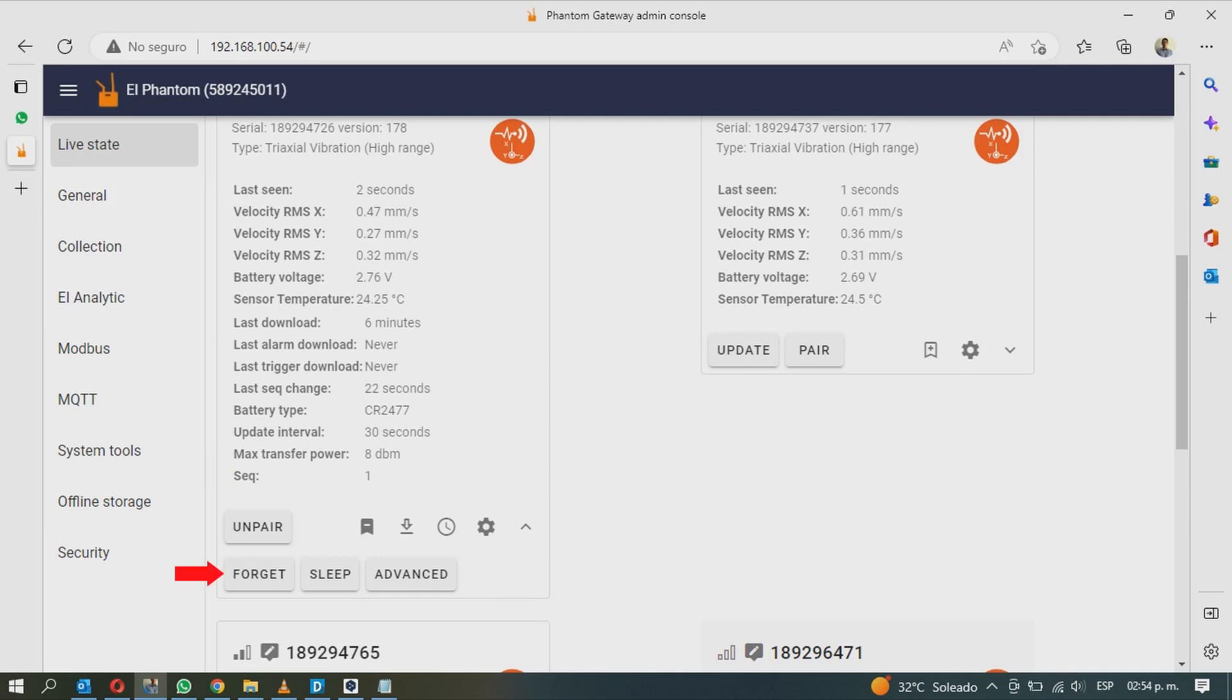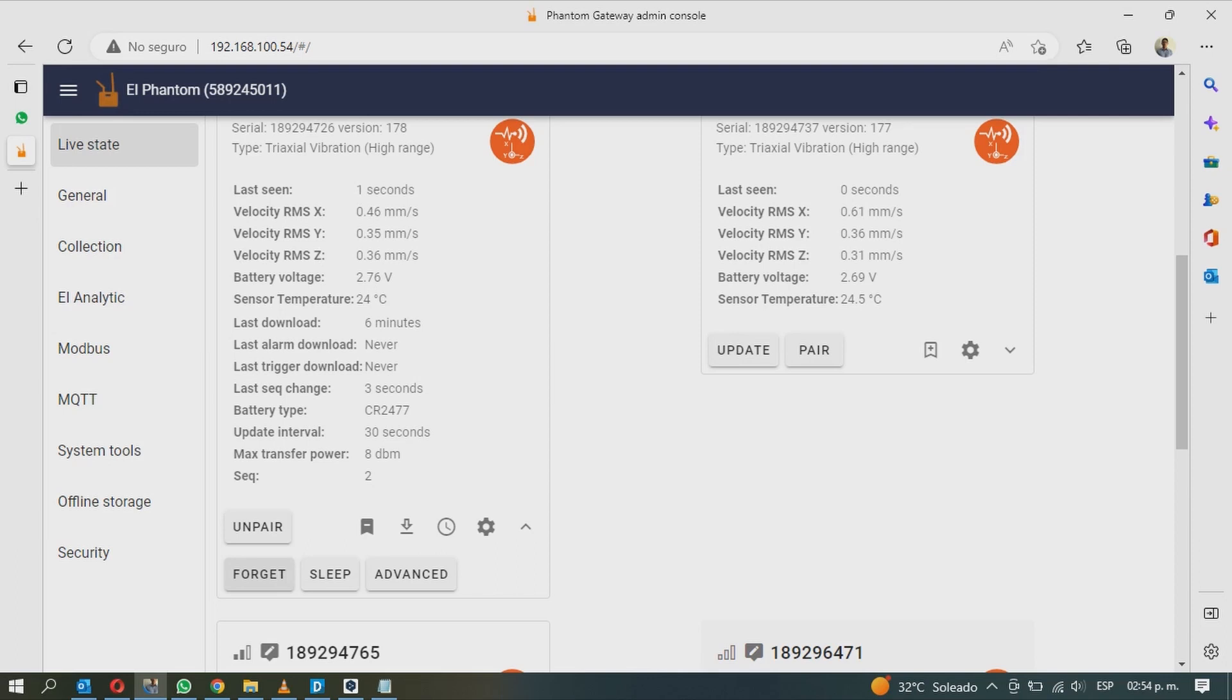Below, you will have three new buttons. The first one is called Forget and it will make the gateway forget the sensor. This way, it will remove the Phantom from the list and you will delete the configurations you have made. This is intended for sensors that you no longer use. If the sensor is still transmitting data, it will appear on the list again, although it will not be paired or configured.